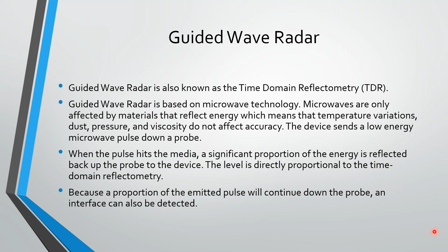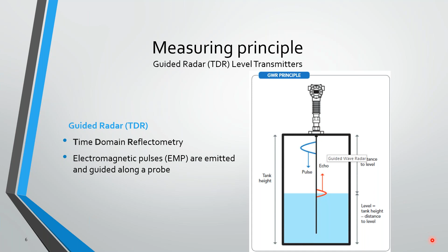So at some point, someone decided we can probably use this same technology to look at the level inside a vessel, which is how guided wave radar level devices came along. Basically, an electromagnetic pulse is emitted and guided along a probe. We see the pulse coming down, and when it hits the medium, we get an echo back and look at the time of travel.